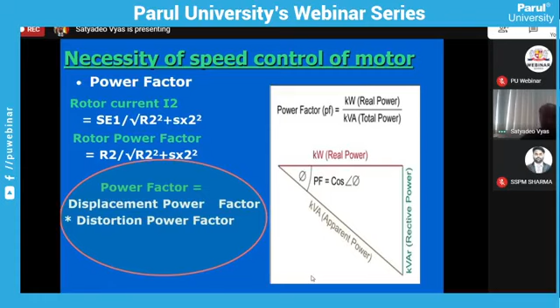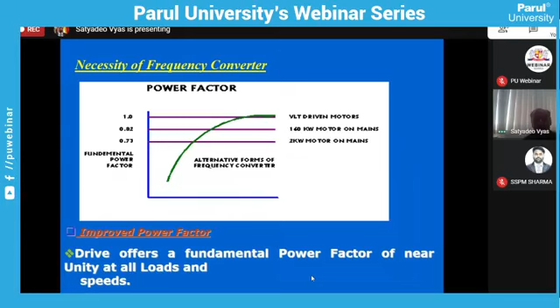Power factor in case of VFD is generally confused with fundamental power factor. Actually, when the diode is conducting, its fundamental power factor means voltage and current are in phase. So the fundamental power factor of the system is 1. When you are using VFD, fundamental power factor is 1. But overall power factor, if you see, will come around 0.97 or 0.98. This drop from 1 to 0.97 is because of the distortion power factor.